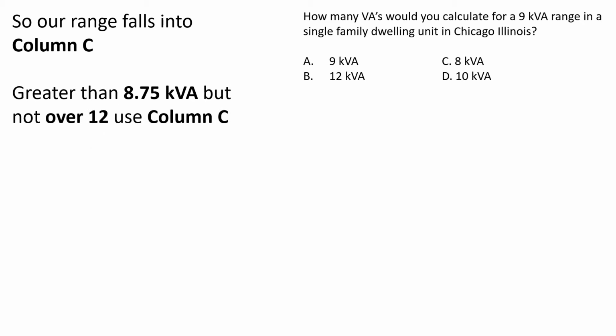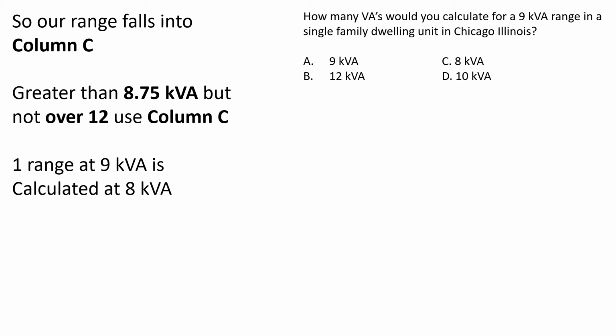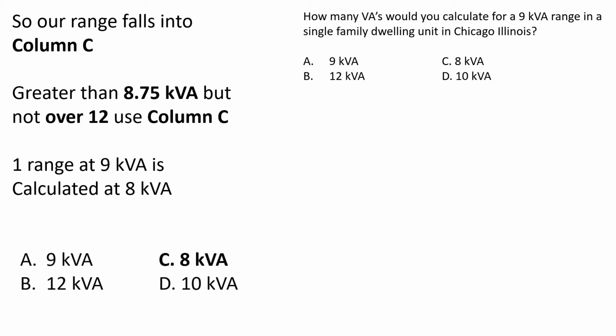Okay, so ours is greater than 8.75 but not over 12. We're going to use column C. We use the left-hand side to select our number of appliances. Then we slide over to column C and we're going to use 8 kVA for our load calculation. We select C.